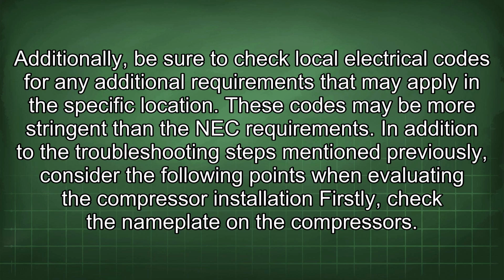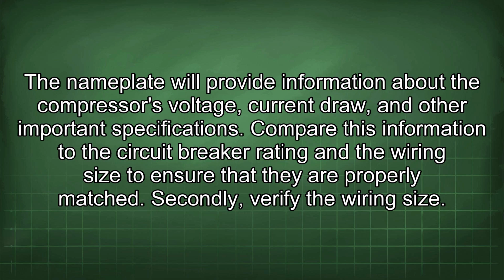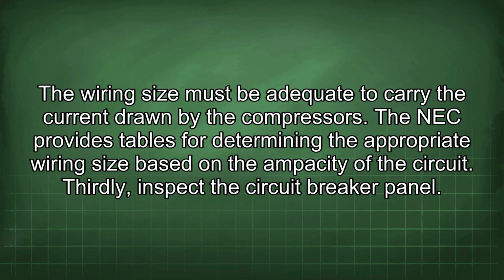In addition to the troubleshooting steps mentioned previously, consider the following points when evaluating the compressor installation. Firstly, check the nameplate on the compressors. The nameplate will provide information about the compressor's voltage, current draw, and other important specifications. Compare this information to the circuit breaker rating and the wiring size to ensure that they are properly matched. Secondly, verify the wiring size. The wiring size must be adequate to carry the current drawn by the compressors. The NEC provides tables for determining the appropriate wiring size based on the ampacity of the circuit.